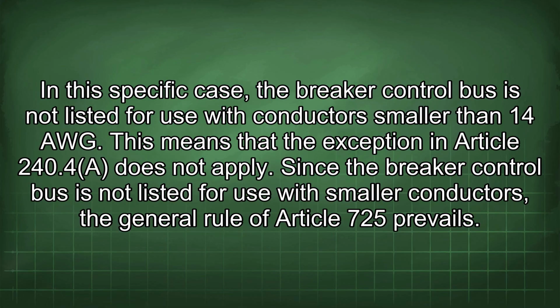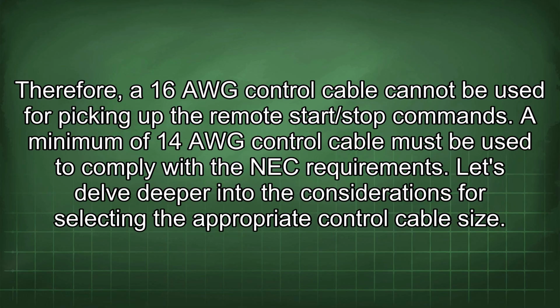Since the breaker control bus is not listed for use with smaller conductors, the general rule of Article 725 prevails. Therefore, a 16 AWG control cable cannot be used for picking up the remote start/stop commands. A minimum of 14 AWG control cable must be used to comply with the NEC requirements. Let's delve deeper into the considerations for selecting the appropriate control cable size.